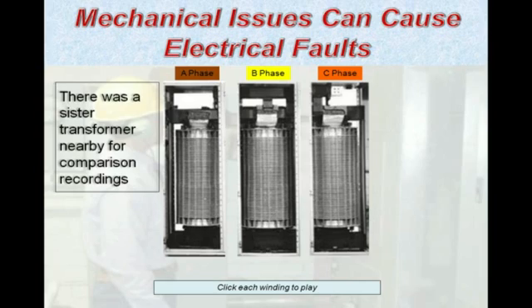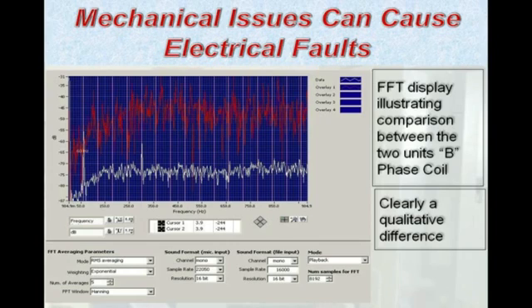So those are all good quality, uniform, and consistent recordings, typically what we would expect on this type of dry type transformer. Now, looking at the Spectralizer software with the recording that was made on the suspect transformer and the sister unit, you can see that the FFT has a comparison between the two B-phase coils.